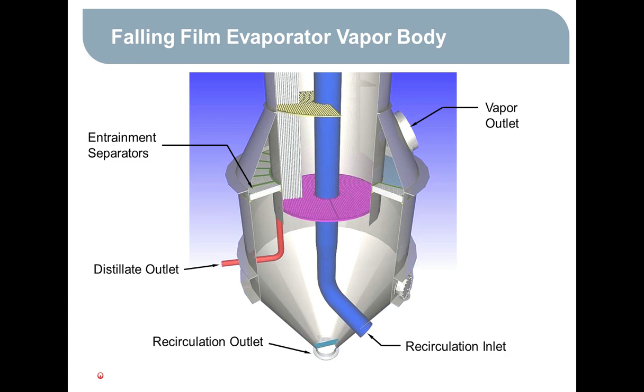There's mist eliminators that go around the top of that vapor body, and the vapor has to pass through those mist eliminators, and they basically scrub out any droplets of water that might be carried along with the water vapor. And so a dry vapor exits at the vapor outlet.